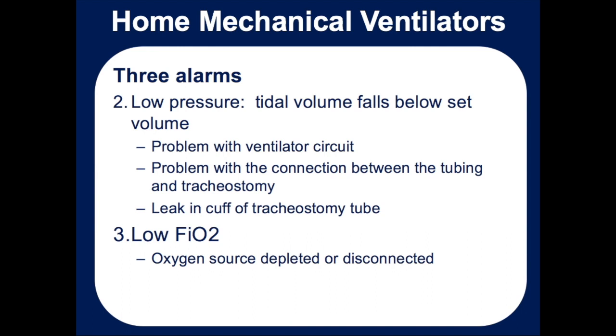And then lastly is low FiO2. FiO2 is just the fraction of inspired oxygen, which is essentially saying that the oxygen source to the ventilator is depleted. It might be something wrong with the tank, or something wrong with the tubing coming from the tank to the ventilator, and the ventilator is sensing it's not getting enough oxygen to give to the patient.